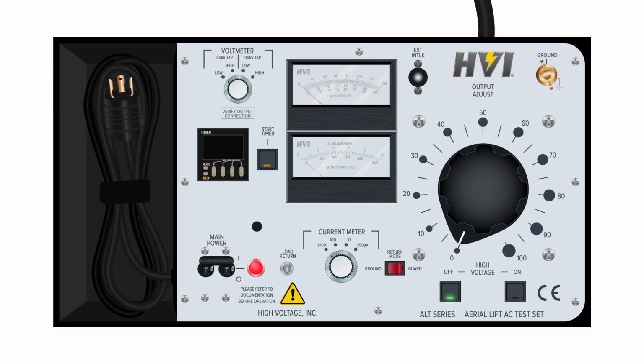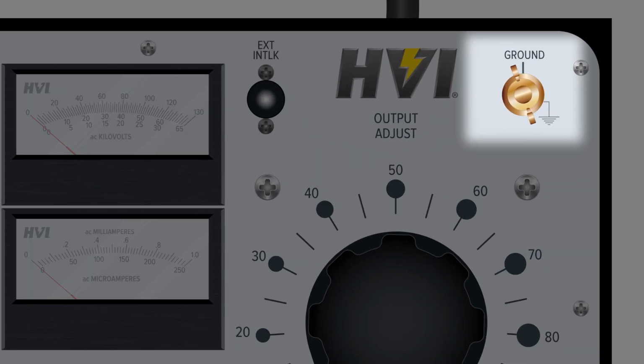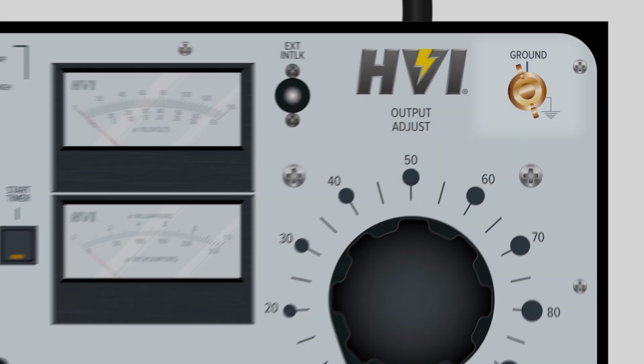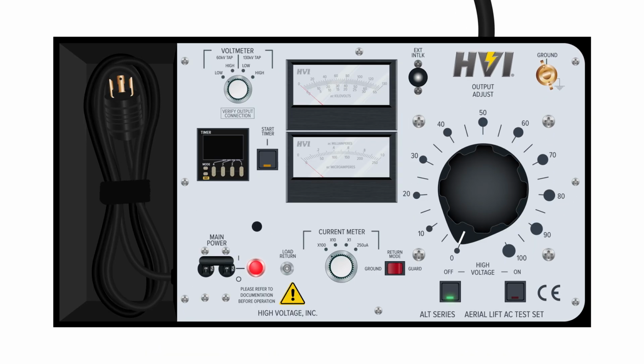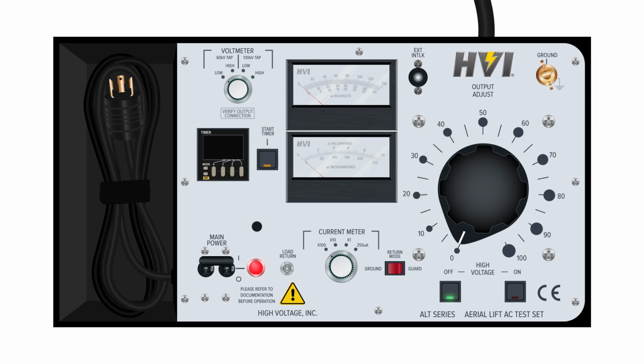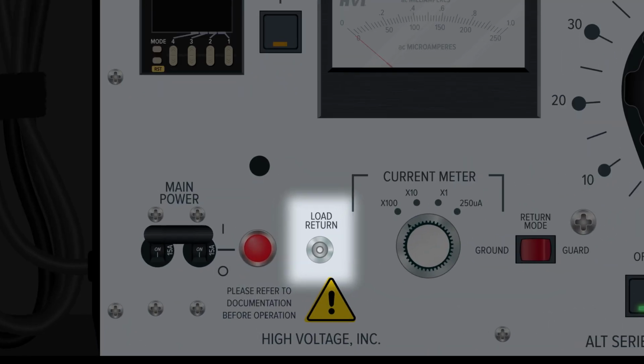ALT series Hipots have three lead connections, one for ground, one for load return, and a customer-supplied high-voltage lead connection. The ground connection is located in the top right of the panel. The ground connection is an important safety element and is used to properly ground the entire device. The load return connection is located at the bottom of the panel and is used to return any current from the DUT through the current meter.